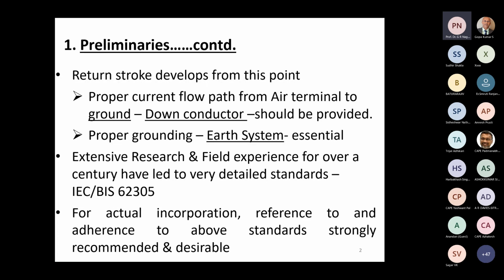So now the proper current flow path from air terminal to ground, that's known as the down conductor, must be provided. So apart from the rod, there must be a down conductor, and then the down conductor must be properly connected to earth. Properly, what we mean, we will see a little later.